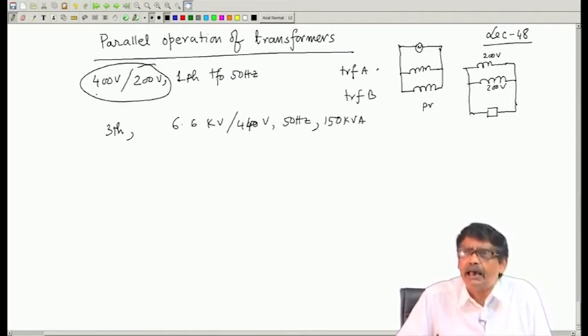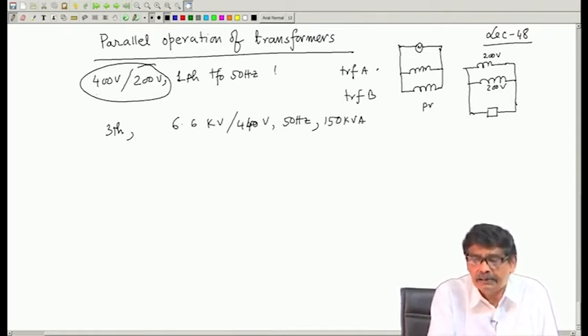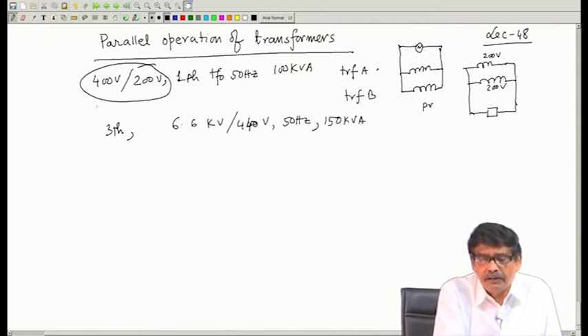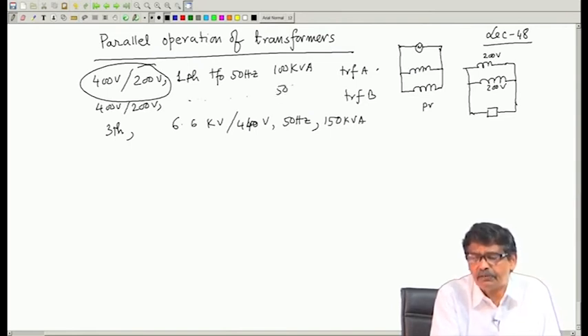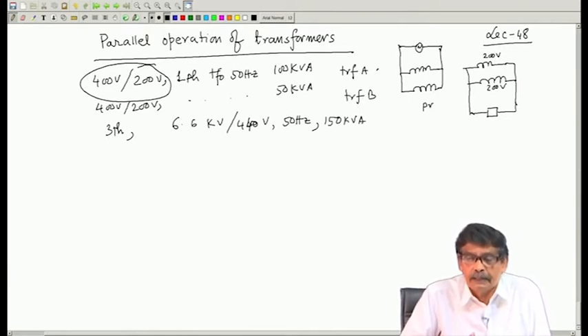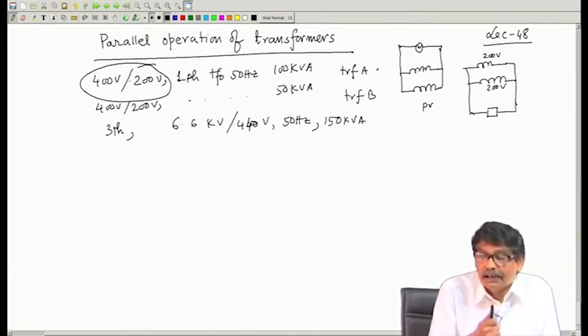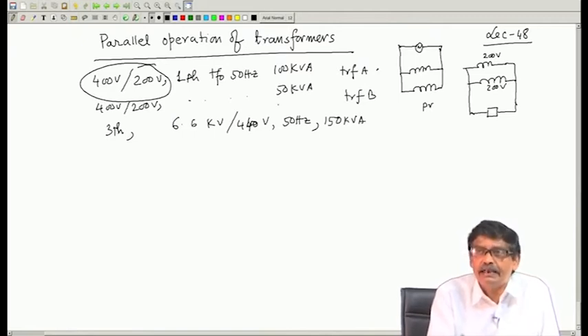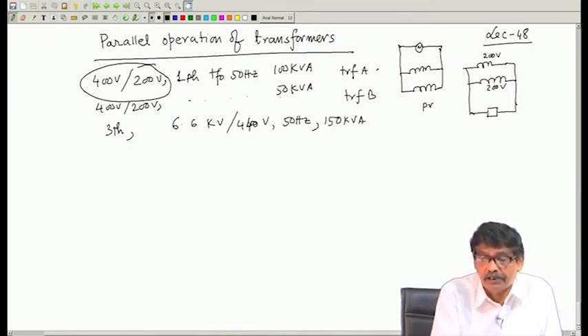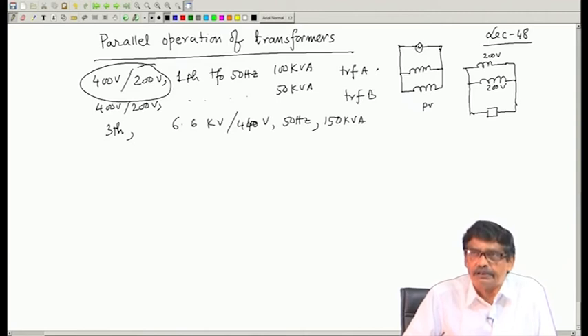One, you may have a 100 kVA transformer, which will be operating in parallel with another transformer of the same voltage rating, say a 50 kVA transformer, no problem, kVA rating may be different. But the only thing is, when they will be operating in parallel, kVA rating means essentially the current rating of either HV or LV. So, you must see that for both of them operating in parallel, the low voltage side should not exceed its rated current. That is the only condition individually. For this transformer, its low voltage current rating will be certainly 2 times this. That should not be exceeded, that is the only thing.